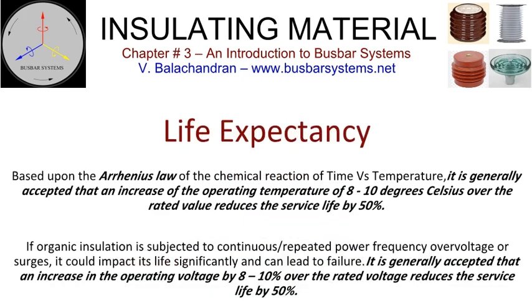Expected life, organic insulations. An insulator made of organic material will decay and has a definite life. The life of organic insulating material is around 20 to 25 years. Any thermal overload reduces its life. Arrhenius law. It is generally accepted that an increase of the operating temperature of 8 to 10 degrees Celsius over the rated value reduces the service life by 50%.